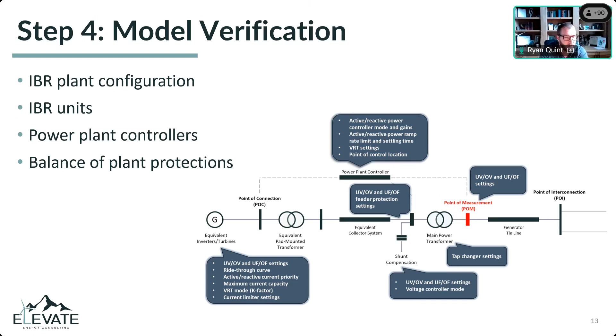And then many of these models don't often have balance of plant relay protections represented. So we're adding those in, and we're mainly focused on voltage and frequency. We're not doing frequency with simulation. It's really focused on voltage, making sure that we've got the collector system and high voltage relays represented, so when we run the simulation, we would see a trip if that protection setting were to trip. We're adding those into the existing model because usually they don't exist. A lot of that's actually helping us prep collectively as an industry for Mod 26, which has some language around protections being represented in the models.